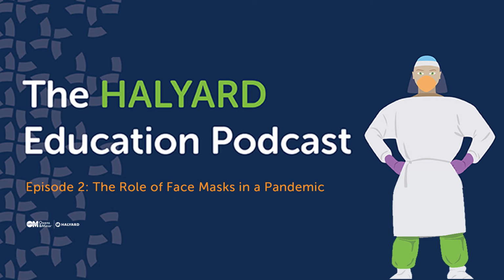Eric, what about medical respirators? How do they differ? So surgical respirators start out by being respirators, so they have to be approved by NIOSH as, say, an N95. But then the FDA looks at them and makes sure that they meet their flammability requirements, that they're not going to ignite and stay ignited, and that they have biocompatibility, so they're not going to cause rashes or irritation. And also they have some level of splash protection for the medical arena.